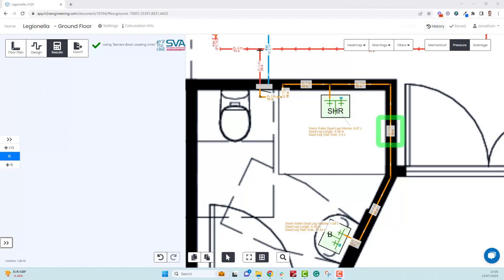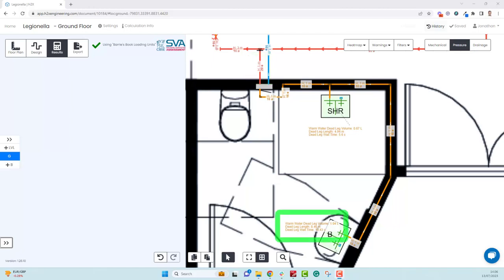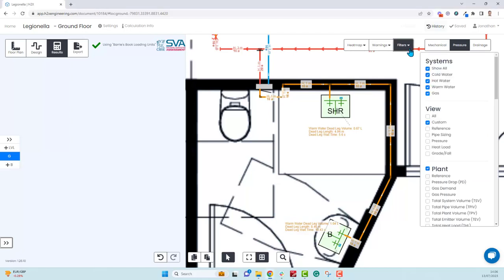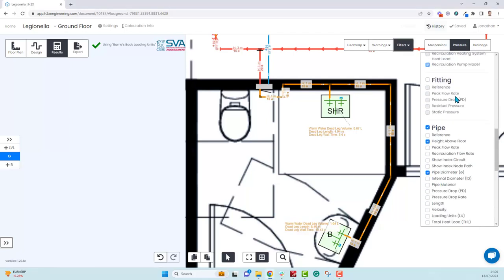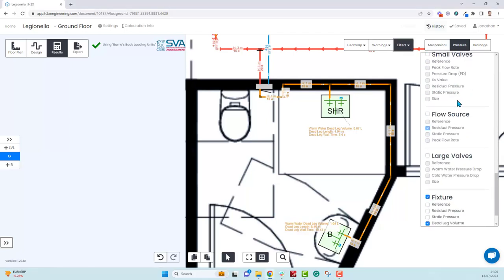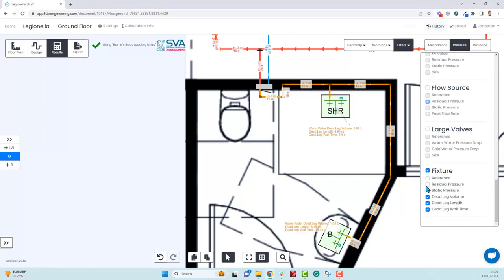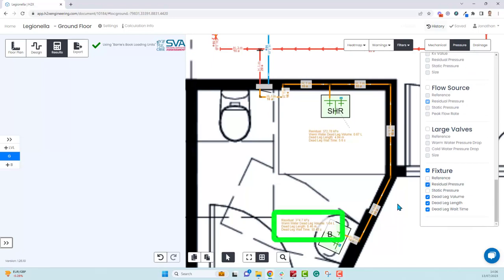This results in a 16 millimeter pipe. But on the hot water system, we have a 1.2 meter per second maximum velocity, and that's given us a 20 millimeter pipe. If we look at the basin again, the volume here is 1.04 liters. Because this change is going to affect the pressure as well, let's turn that on at the fixture. You can see we're getting 374.7 kPa.